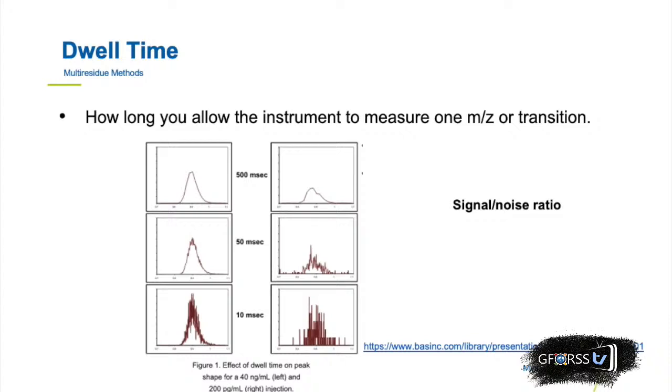In theory, the signal-to-noise ratio improves according to the square root of the additional time. So moving to 100 millisecond dwell time should improve the signal-to-noise ratio by 3.16 times. Considering the margin of error, this is approximately the dwell time that would be needed to obtain a peak with a signal-to-noise ratio of 10, the minimum requirement for a quantitative measurement.